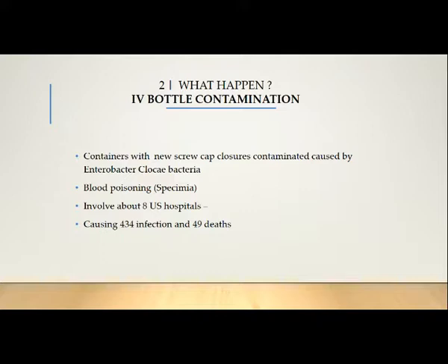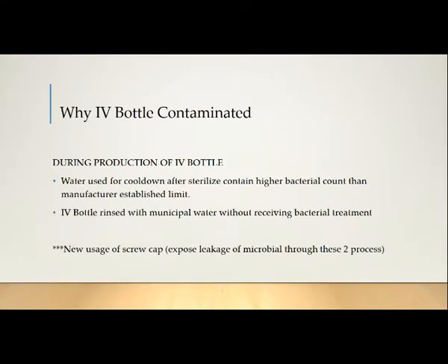So why was the IV bottle contaminated? During production of the IV bottle, the water used to cool down after sterilization contained a higher bacterial count than the manufacturer's established limit. IV bottles were also rinsed with municipal water without receiving bacterial treatment. So, from the new usage of the screw cap, it exposed leakage of microbes through these two processes.